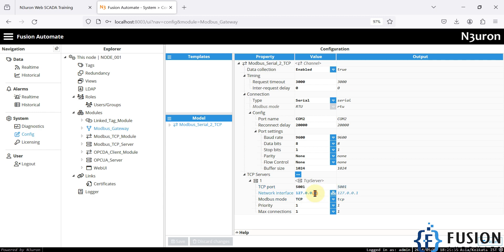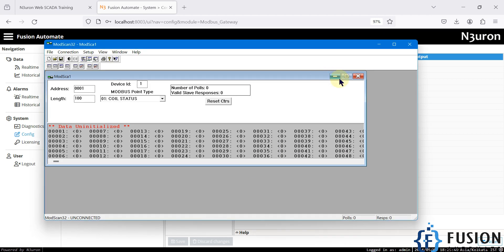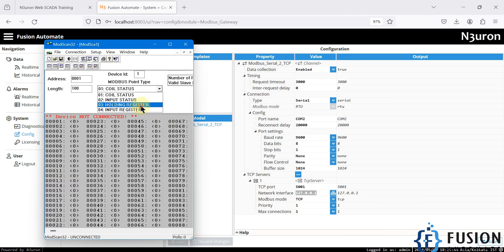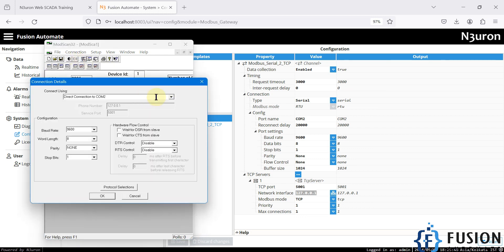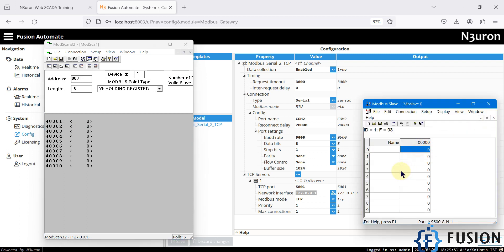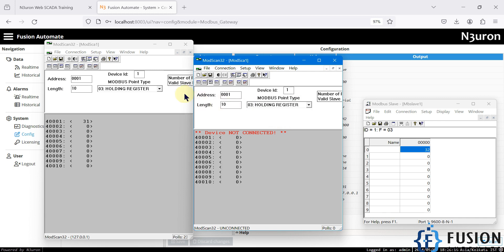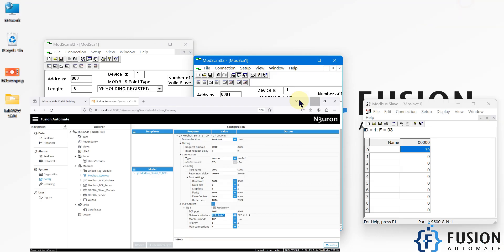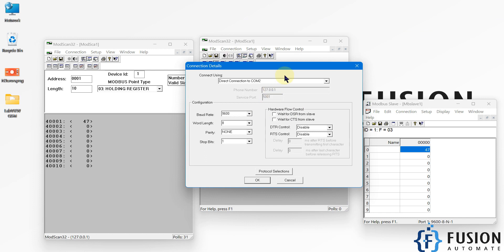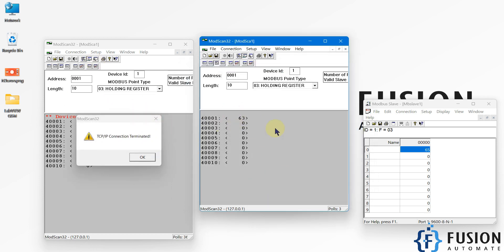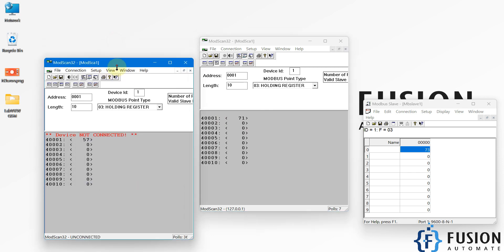All data is now available on port 5001 at network interface 127.0.0.1. I'll open my ModScan software — a Modbus client — select holding registers with length 10, and in the connection select remote Modbus TCP server port 5001. You can see it is connected and the value of the first holding register is updating. If I launch a second instance of ModScan and try to connect to the same TCP server on port 5001, it won't allow it — the connection gets terminated.